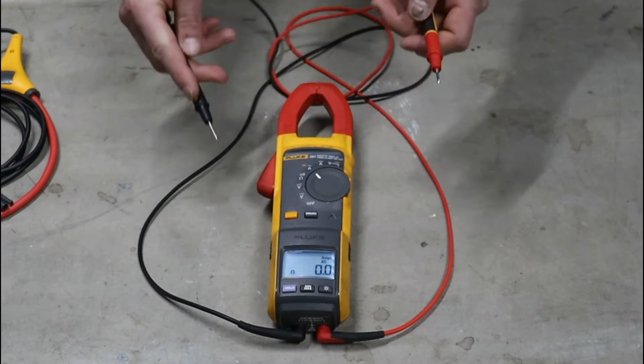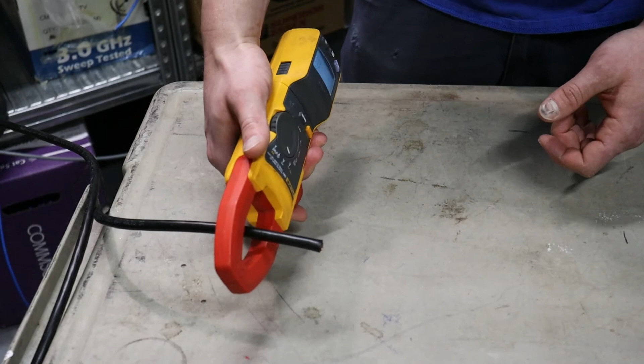Here we're going to go over the amperage AC. I've turned the dial to amps AC. I've got a little test wire here to show you how to properly clip onto a wire to measure. So you see the little red trigger here, that actually opens up the jaw. In most cases in the field, you're going to see this terminated, so you're not going to be able to slide it on like that. You're going to have to clip it on. And when you do, you want your little dashes. You can see there's 2 dashes on there. You want those to center of the conductor, so it's right in the middle of the probe for more accurate and precise readings.